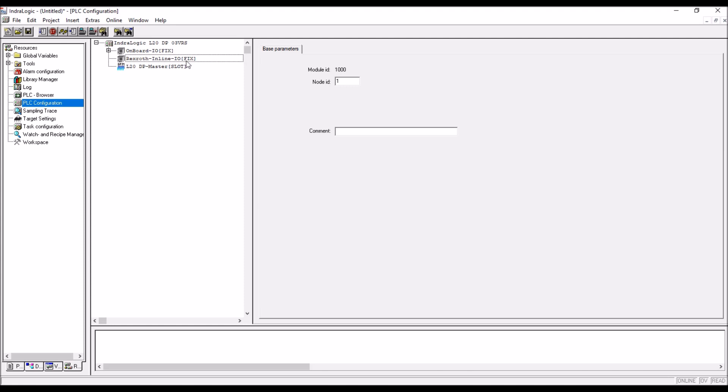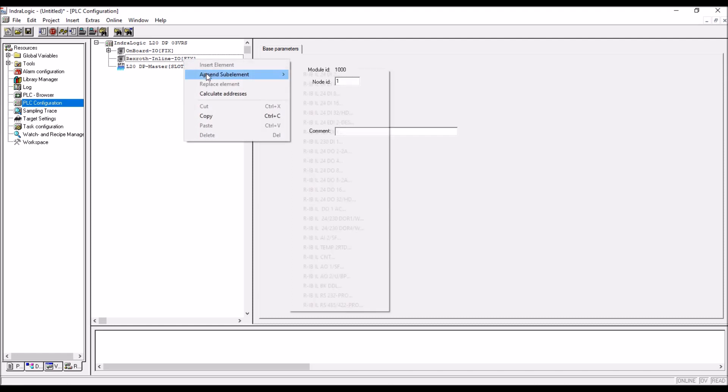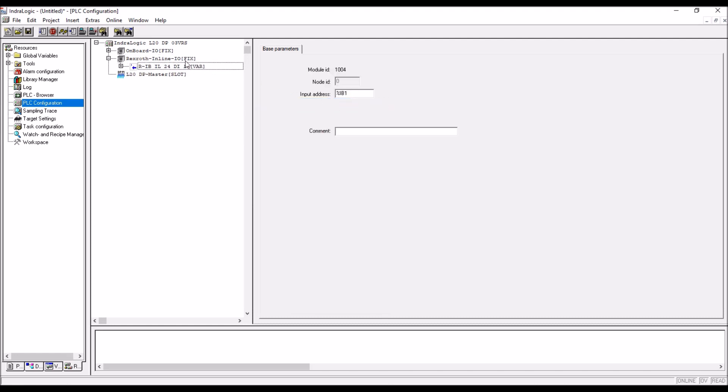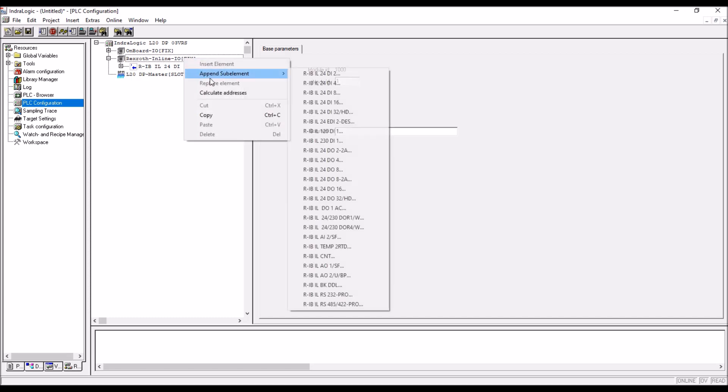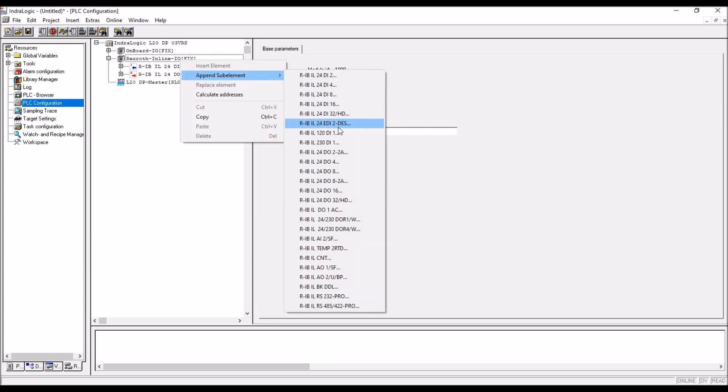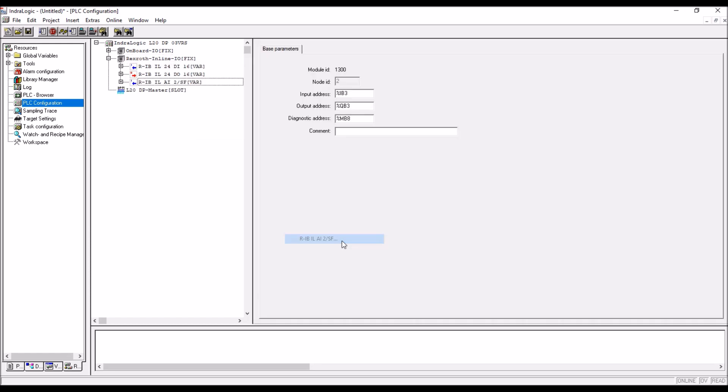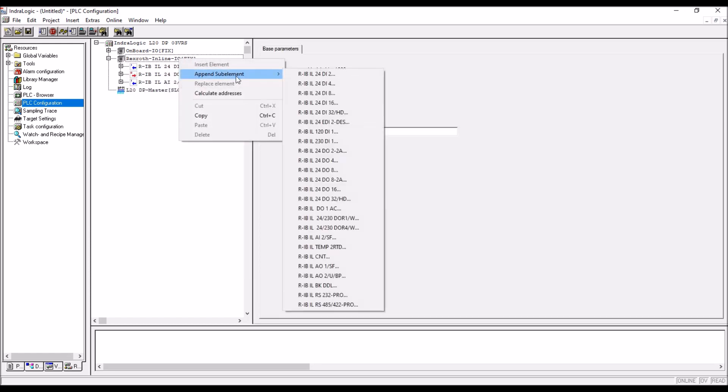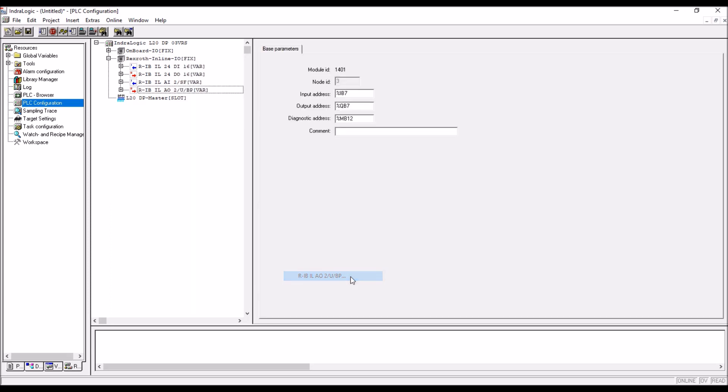If inline is empty, but hardware has got real extension, then there definitely there is an error, that is called RI error. To avoid that, right click on the inline, append sub-element. There DI16 you take it, and then DO16, and then AI2, next AO2 slash U slash BP, you have to take it.